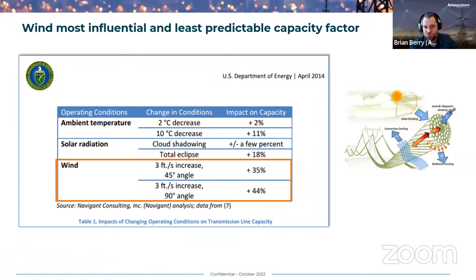But wind, with 3 feet per second — that's about 1 meter a second, like walking speed in the street — very low wind, hardly any wind actually. If it's perpendicular to the line, you get plus 44% extra capacity. Massive — we're saying you can push 44% more current through that line. So you could have 1.5 power stations' worth from the same line, just by considering wind. That's huge, right? Huge saving.